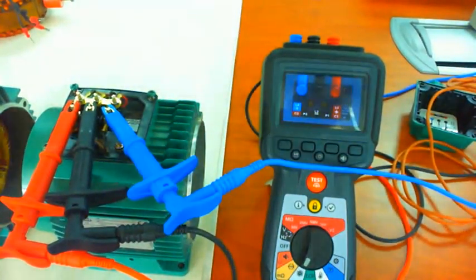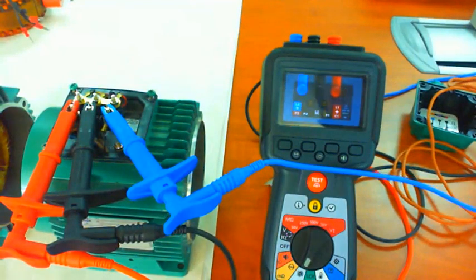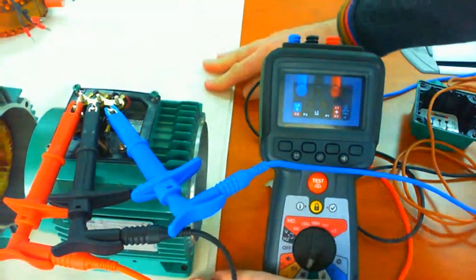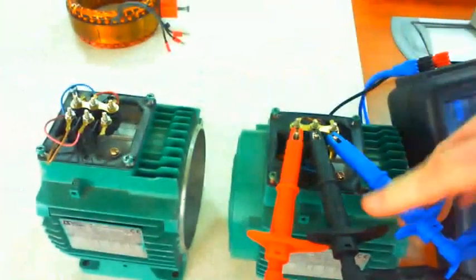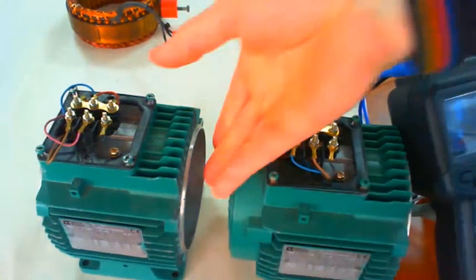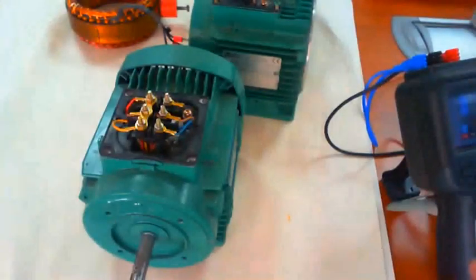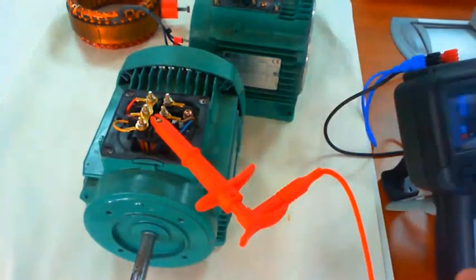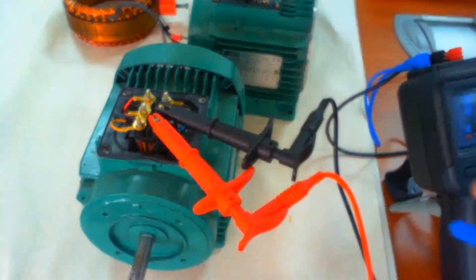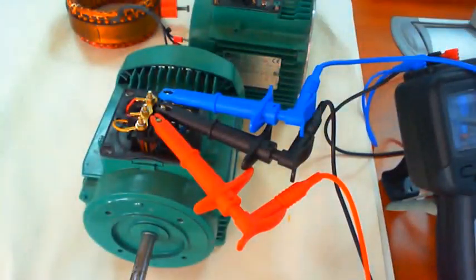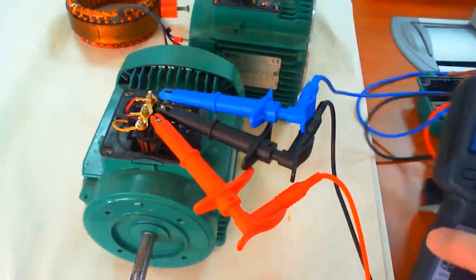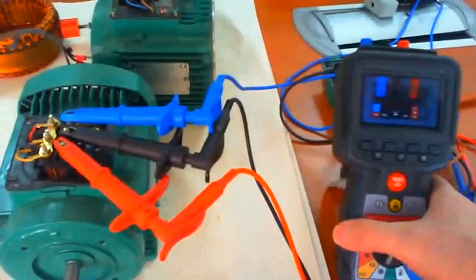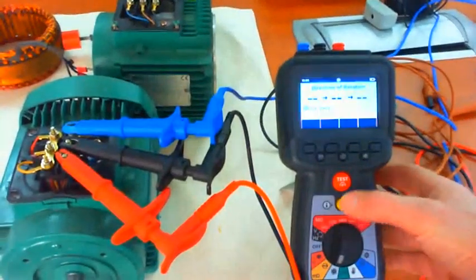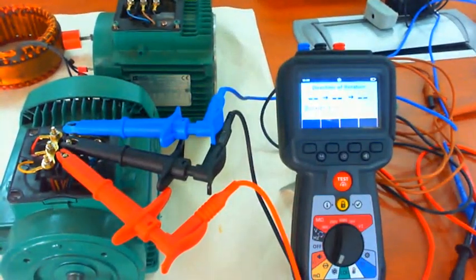And actually I do want to change that motor. So let's get rid of these 2 and bring in my assembled motor. Obviously we need the rotor fitted to be able to run this test. So red to L1, black to L2, blue to L3. Okay. Press lock. So we have our direction of rotation.